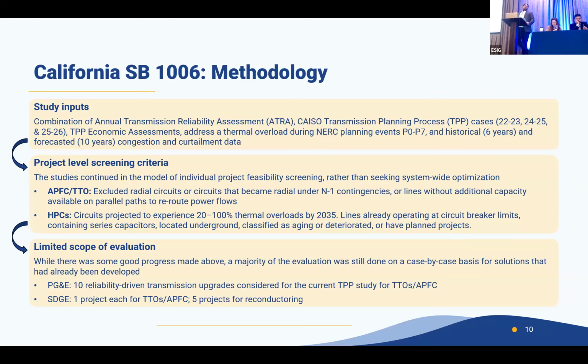So just as some basic examples, APFC or transmission topology optimization were excluded when the lines they were looking at were radial lines that weren't meshed with the rest of the system. That's a good screening criteria because it doesn't allow for power to be redistributed. As an example, for high performance conductors, these can typically increase capacity by up to maybe 75 or 100%. So any circuits with thermal overloads between 20 and 100% were among the screenings being developed.